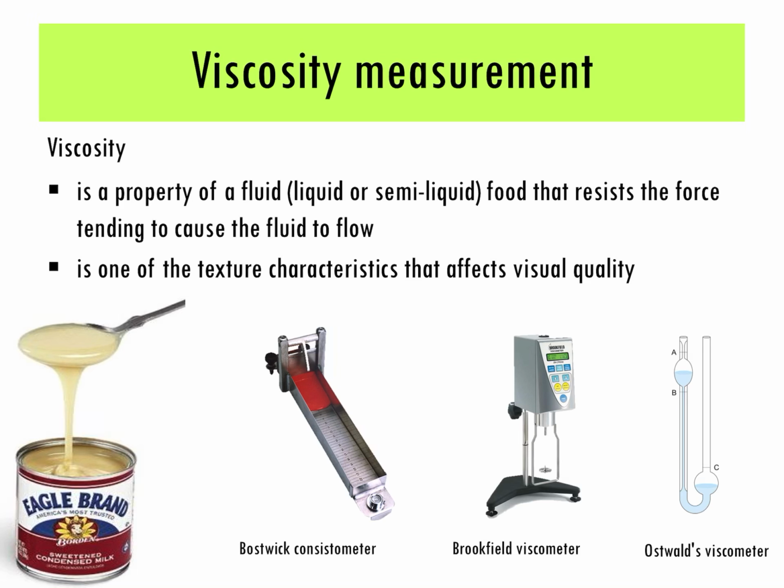The equipment acts like an inclined surface, and tomato paste will be filled in the back chamber of this equipment. Once the blade comes up, the tomato paste will travel through the inclined surface, and then we can fix the time and measure how far it can go, or we can fix the distance and measure how long it takes to move that distance. And this one will represent how viscous the sample is.